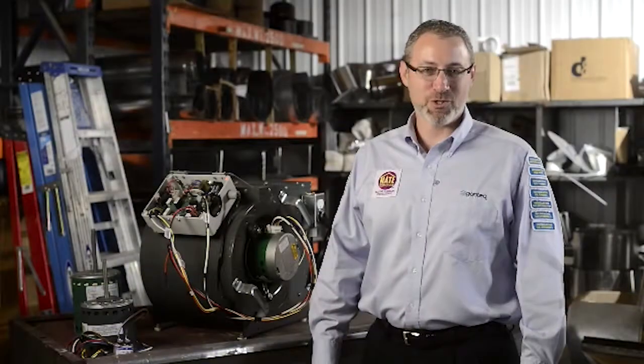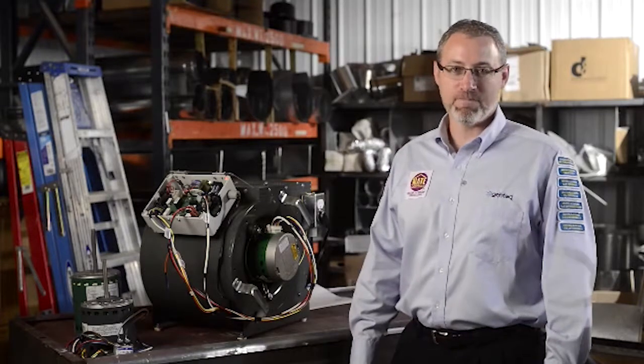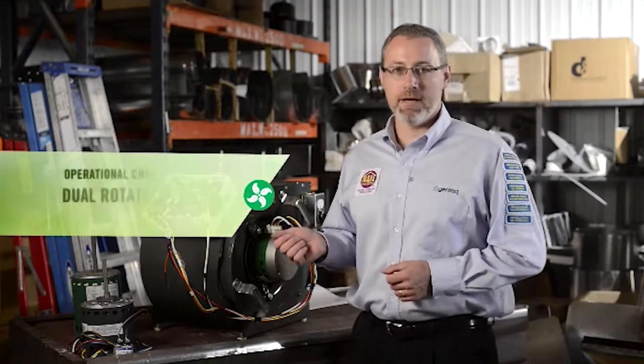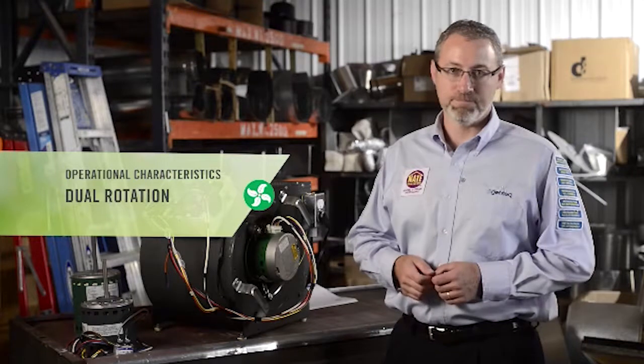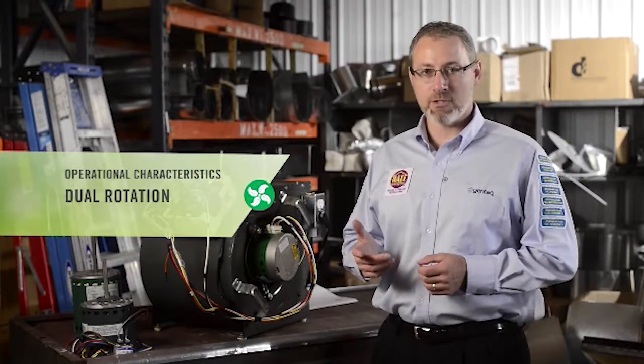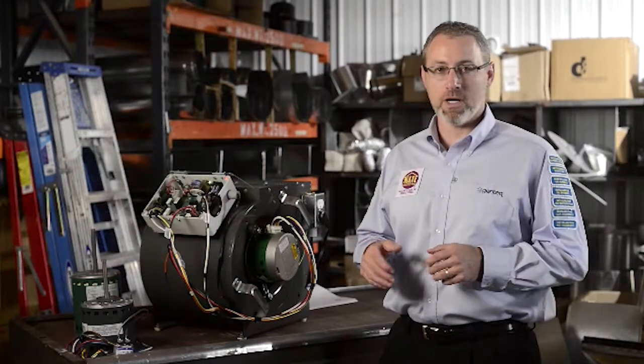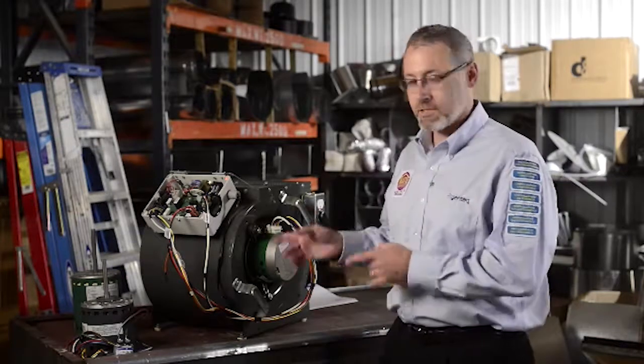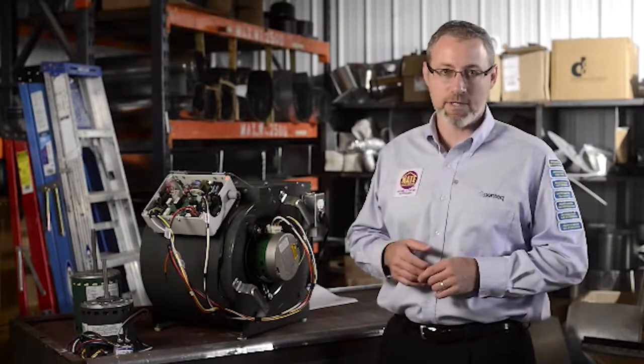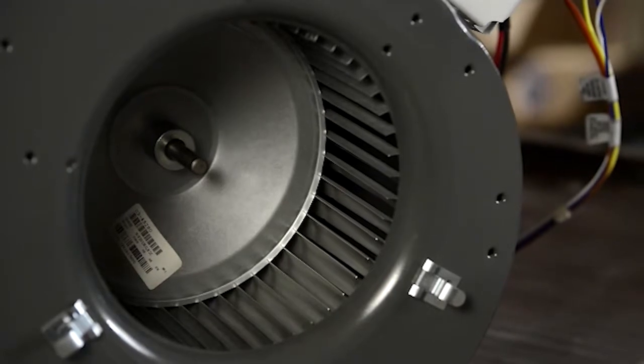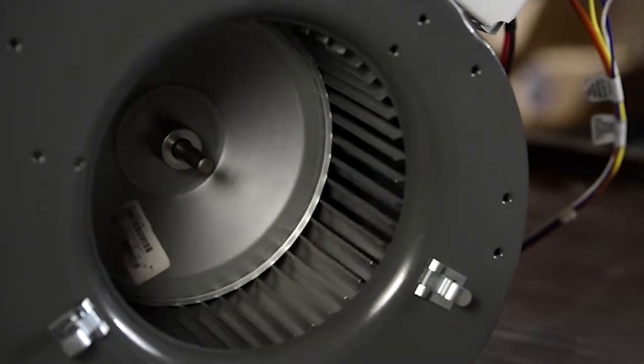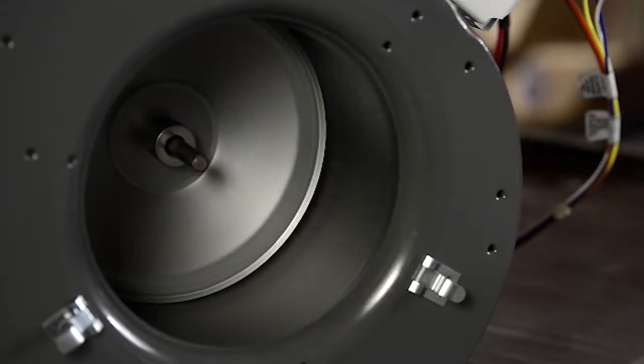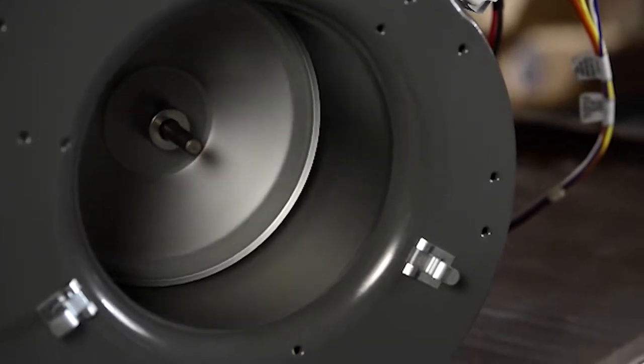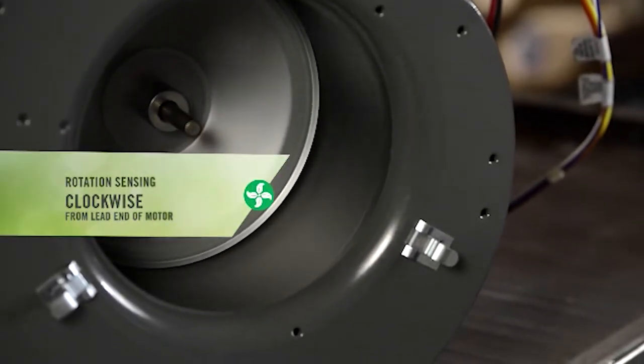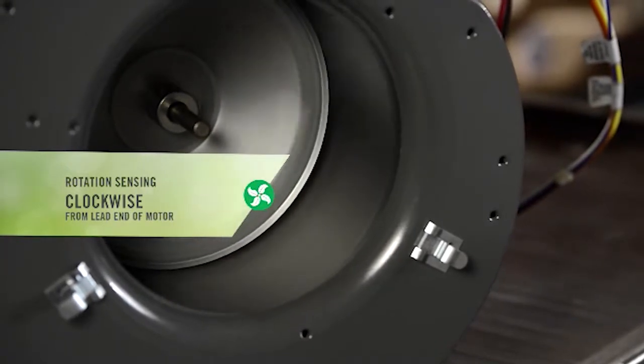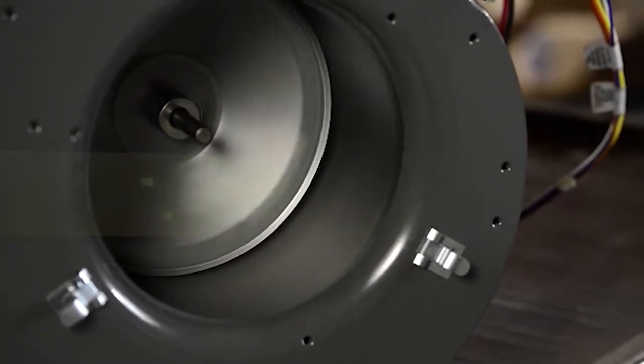Let's talk about operational characteristics and features. If you remember, we mentioned that the Evergreen IM is a dual rotation motor. The first time it turns on, it's going to run both directions to automatically configure itself to the rotation of the blower wheel in your HVAC system. So let's look at how that works. On the first demand call, the motor is going to turn on, and it's going to run clockwise for about 10 to 15 seconds at a very slow RPM.